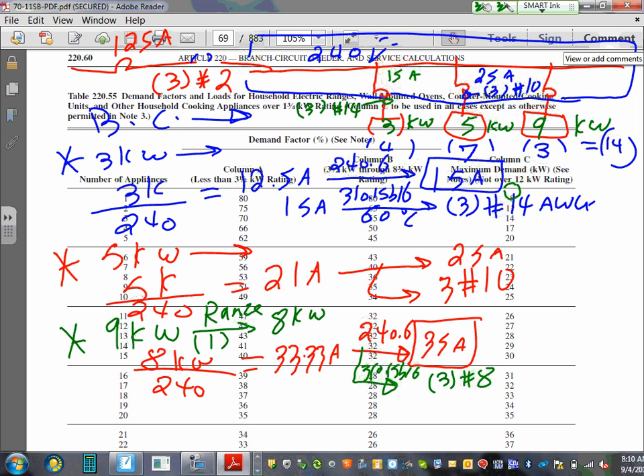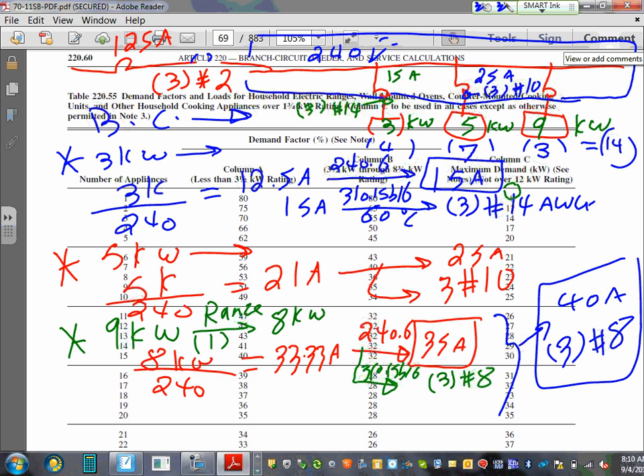There's one little problem here. Not a problem, an exception in the code. It says branch circuits, guys, if they are larger than 8 3/4, regardless, you cannot use less than 40 amp. So because of this exception, I have to use 40 amp for this and 3 conductors. Number 8 still gets me there, right? Number 8 still gets you. And this is from 210.19(A)(3). It will tell you if your range is 8 3/4 or larger, regardless of what your calculation comes up with, we don't want you to mess around, use 40 amp. That's why the 35 became a 40.